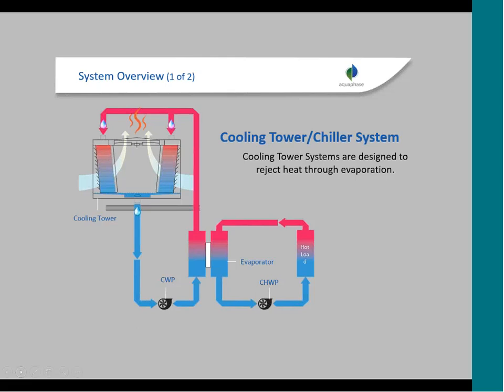Once the heat is transferred to the refrigerant, it's taken to the condenser side of the chiller. From there, the heat is taken from the condenser water out to the cooling tower, where it's released to the environment. So we're just taking heat from where we don't want it and removing it to the atmosphere—that's what these water systems do.